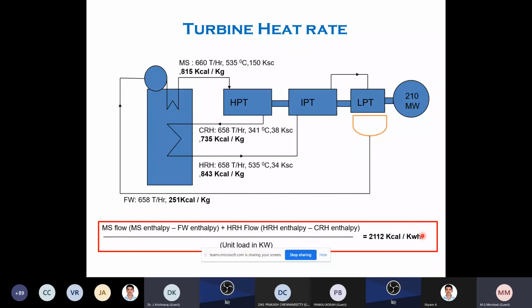So this is the total flow diagram for measuring the turbine heat rate. These are the things you have to see: what is the MS condition, what is the cold reheat, hot reheat, feed water. By using this formula: MS flow into the difference of MS enthalpy and feed water enthalpy, plus hot reheat flow into the difference of hot reheat enthalpy and cold reheat enthalpy, divided by the unit output. So the turbine heat rate will be calculated: 2112 kilocalorie per kilowatt hour. This is the method of calculating turbine heat rate by taking the data from the unit control room.